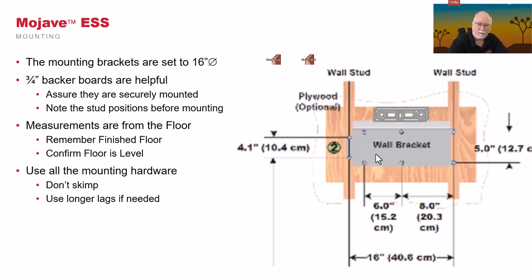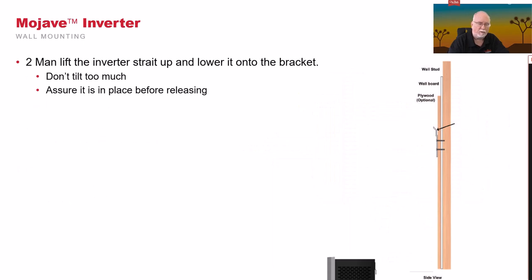And the one thing that I always ask people to do too, if you put up a backer board or if you have bracing behind it, these screws have to go in again, maybe a 2-inch, 2.5-inch lag. Then use our remaining bolts to back it and put it in place. The reason I mention this is that this unit's going to be in place for 10 years, right? It's got a 10-year warranty. I don't want to be revisiting it because it's getting loose on the wall or something silly like that.